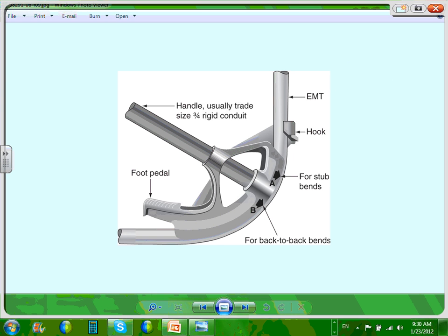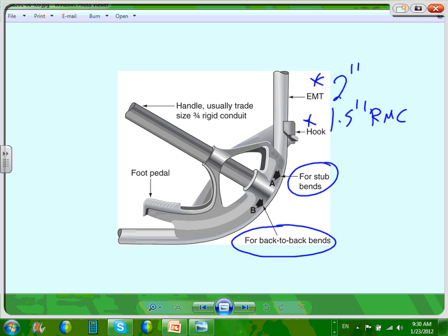Usually you can bend, if it's a bender, you can bend 2 inch EMT, then 1 and a half inch rigid metal conduit. Good luck doing that. So anyway, just be aware, guys. I don't go over this one with the designers. There's a couple of ways you have to be aware when you bend the conduits, the location of how to bend the 90 stub ups and so forth.